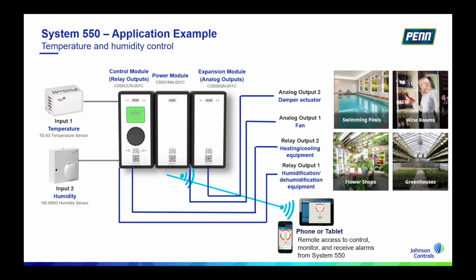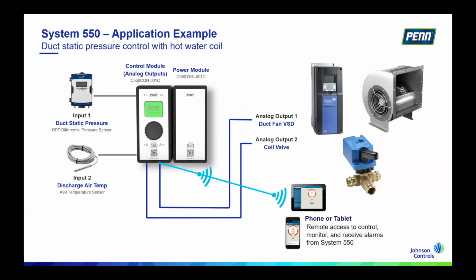All right, if you want to move to the next one, Josh. So this is one using a combination of air temperature, discharge air temperature, and duct static pressure. It's very simple where we have those two analog outputs. One is controlling a variable speed drive, and the other one is controlling the actuator that's mounted to a three-way valve. And again, you're connected to the cloud, or can be connected to the cloud.